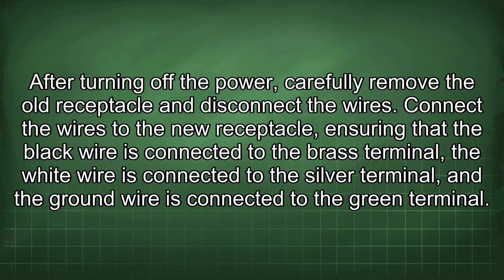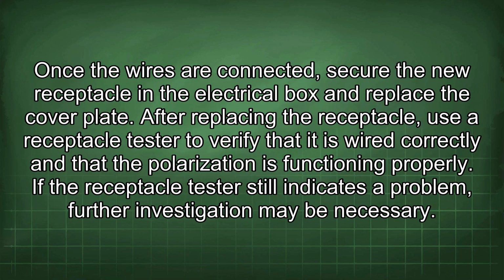Connect the wires to the new receptacle, ensuring that the black wire is connected to the brass terminal, the white wire is connected to the silver terminal, and the ground wire is connected to the green terminal. Once the wires are connected, secure the new receptacle in the electrical box and replace the cover plate. After replacing the receptacle, use a receptacle tester to verify that it is wired correctly and that the polarization is functioning properly. If the receptacle tester still indicates a problem, further investigation may be necessary.